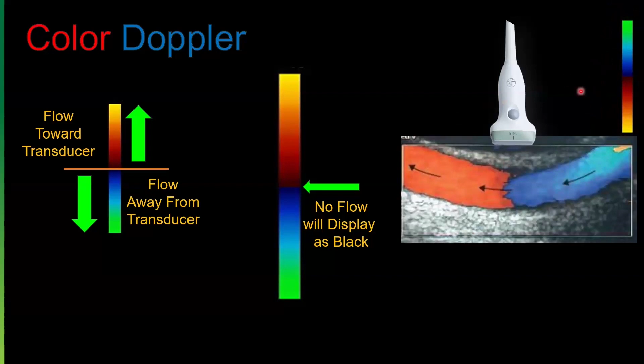So take a look at the scale. Remember, I said the first thing you want to do is have a look at that scale over here on the side, because what this is telling me now is that blue flow is toward the transducer and red flow is away from the transducer. And again, that's a parameter, a setting that you can do as the operator. So the orientation of the display, red toward blue away, or blue toward and red away, is at the discretion of the operator, you.